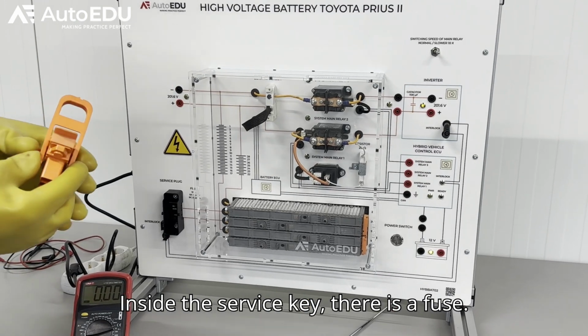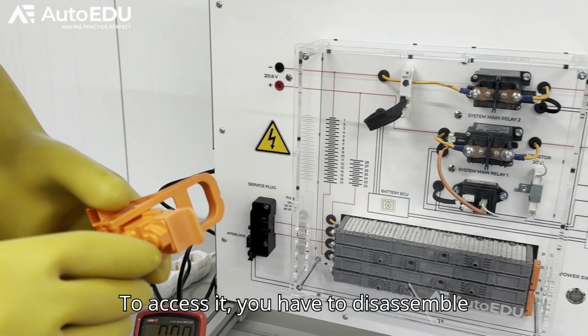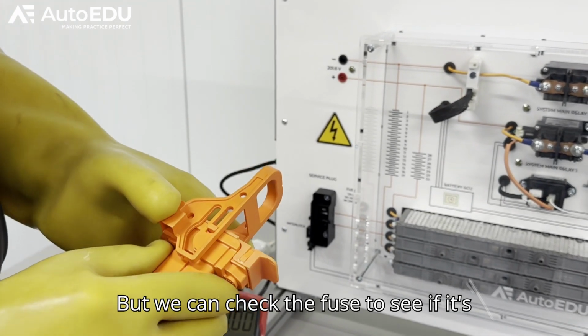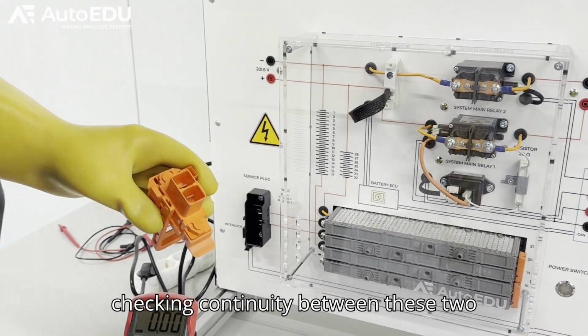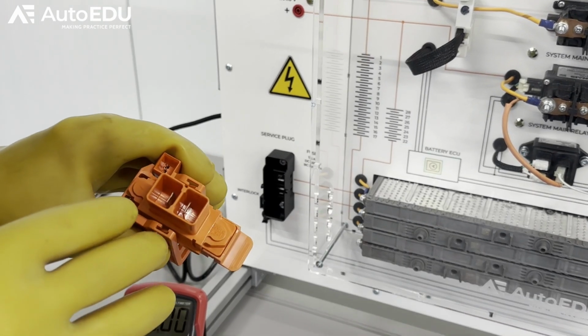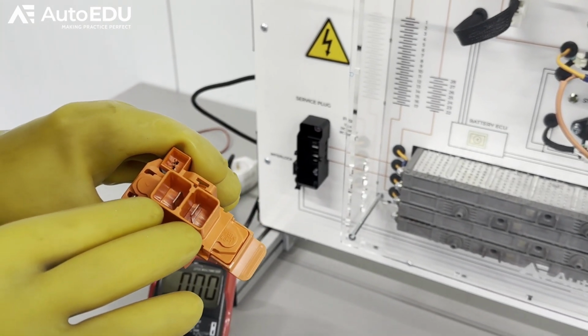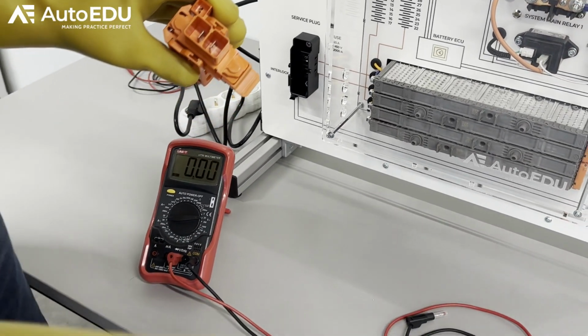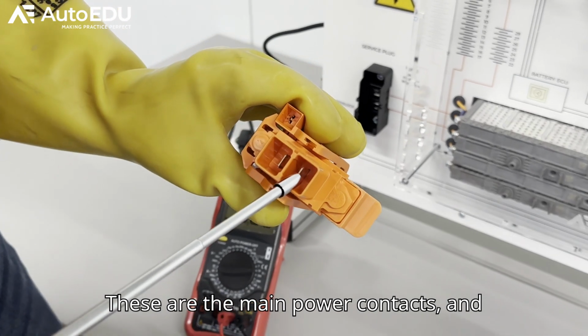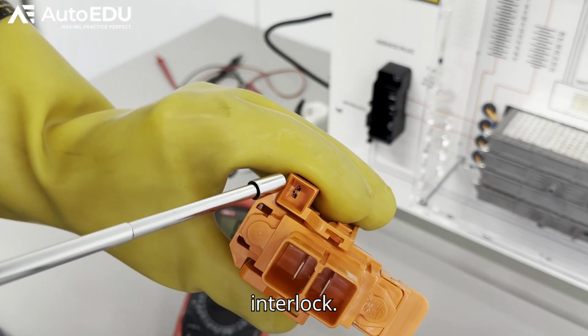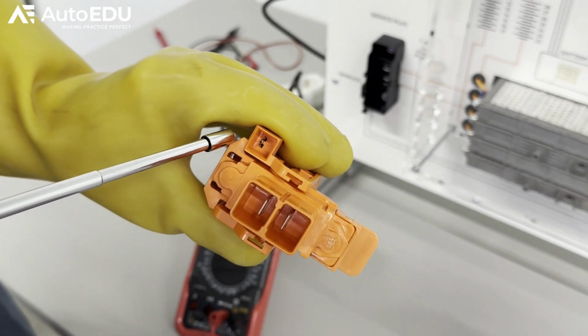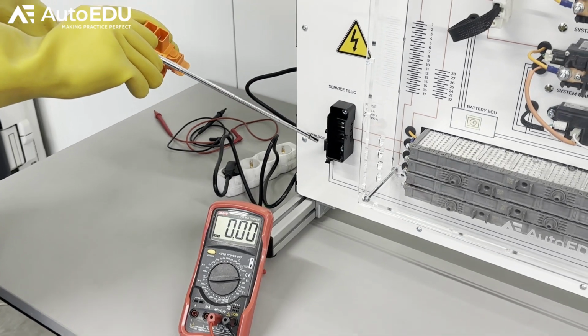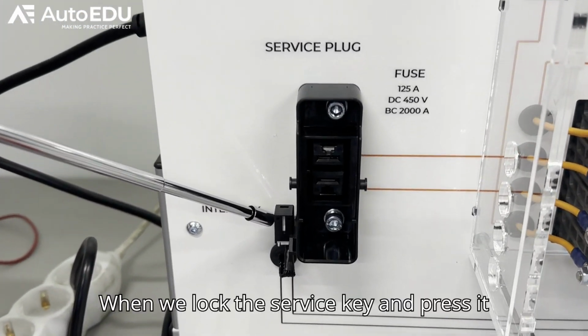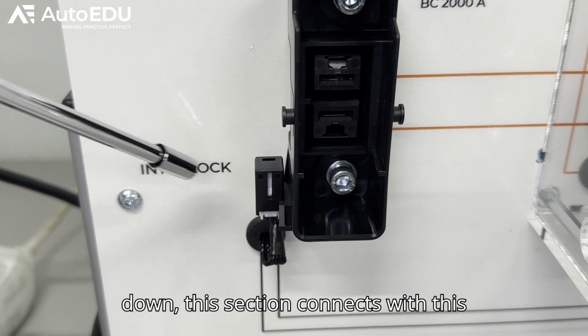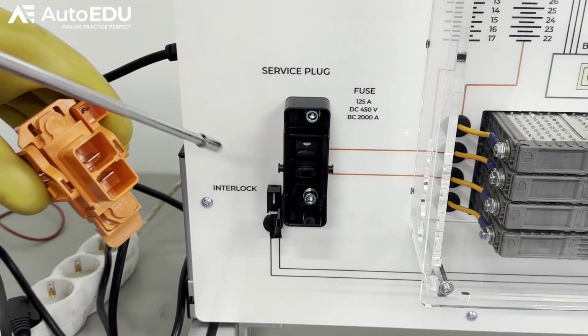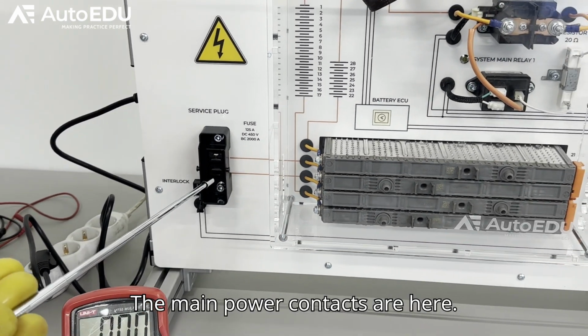Inside the service key, there is a fuse. To access it, you have to disassemble everything here. But we can check the fuse to see if it's good simply by measuring voltage and checking continuity between these two main contacts. These are the main power contacts, and these are two smaller contacts called interlock. The interlock contacts are here on the side. When we lock the service key and press it down, this section connects with this part. The main power contacts are here.